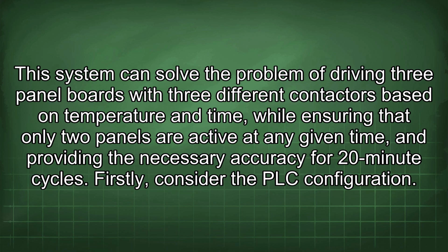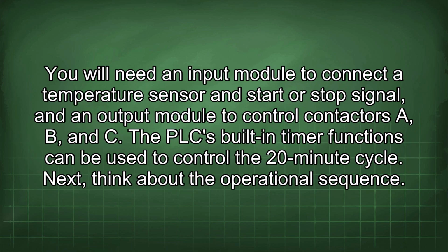Firstly, consider the PLC configuration. You will need an input module to connect a temperature sensor and start or stop signal, and an output module to control contactors A, B, and C. The PLC built-in timer functions can be used to control the 20-minute cycle.